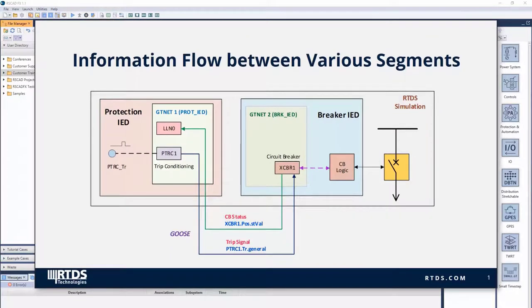This figure shows the information flow between various segments of the simulation. The breaker IED includes simple controls that enable opening and closing of the circuit breaker based on internal push button from runtime, or an external trip signal received from the protection IED via GOOSE communication. Similarly, the protection IED receives the status of the breaker from the breaker IED in the form of a GOOSE message. There exists a real Ethernet communication link between two GTNet X2 modules which facilitates the exchange of GOOSE messages.